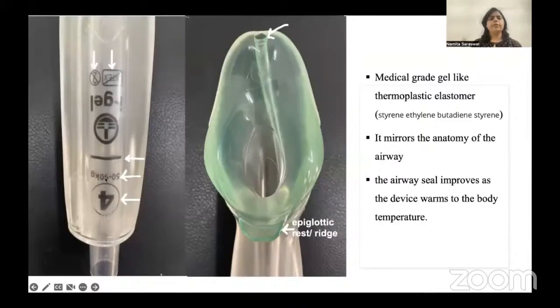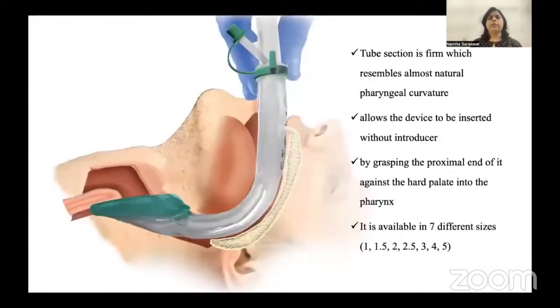This is a size 4 device which can be used in a 50 to 90 kg patient. Here also so much information is given. It is made up of medical grade thermoplastic elastomer, and it mirrors the anatomy of the airway. It also provides a dynamic seal, so it also falls in the category of third generation. The airway seal improves as the device warms to body temperature, so with time the seal will improve. Because it has a rigid airway tube, no tool is required to insert the device. It can be put directly along the anatomical curvature. It is available in 7 different sizes.